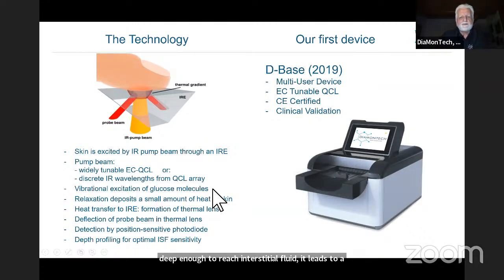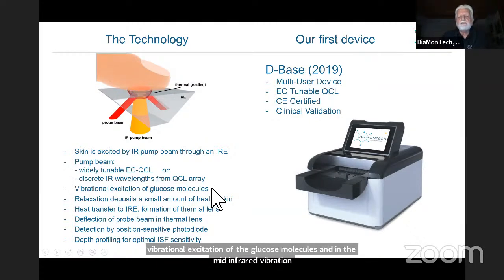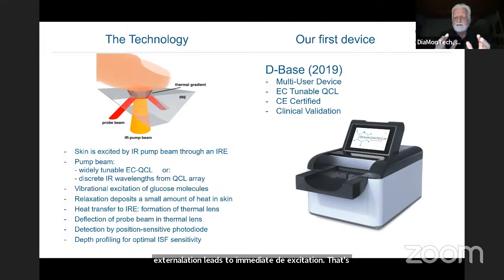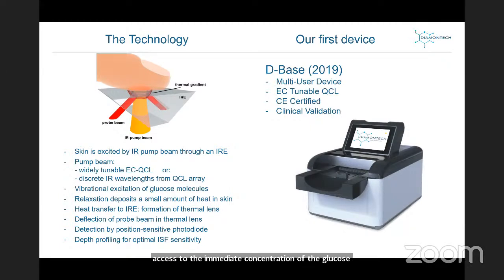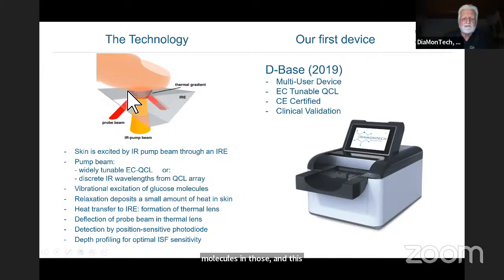And in the mid-infrared, vibration excitation leads to immediate de-excitation. That's about 10 to the minus 12 seconds. That's really fast. And it leads to a deposit of a small amount of heat in skin. And the small amount of heat in skin layers is proportional to the excitation power, and it's proportional to the glucose concentration. So as we control the excitation power, we have an access to the immediate concentration of the glucose molecules. And this heat deposited in skin transfers to the internal reflection element.